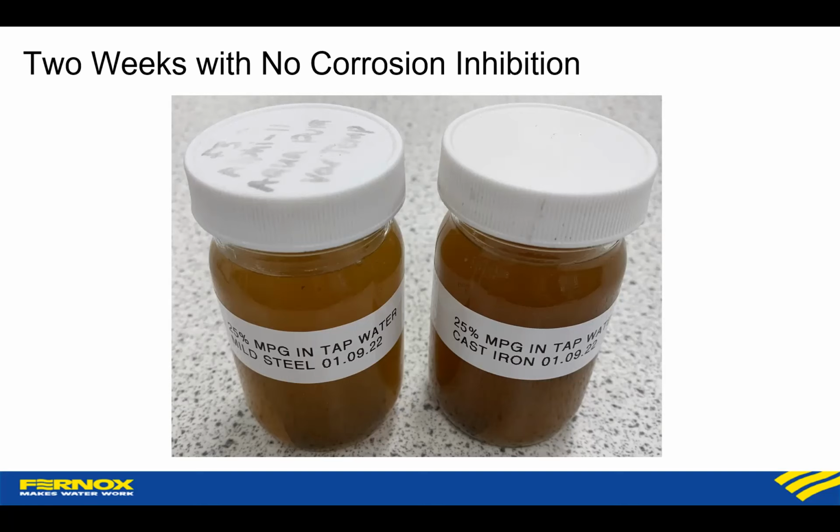So in conclusion, this was just a simple test to show how quickly cast iron can corrode in a water glycol mix that you might find in a ground source heat pump ground loop.